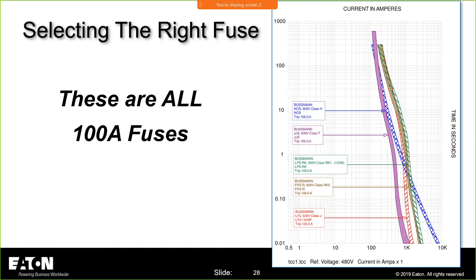So this is your Class T. Remember I said love at first sight? Look at that fuse curve. It's very fast. It's moved over to the left. This is a 100 amp fuse. I still get a nice little delay in here. So if I had a motor starting curve, or if I had an inrush current, maybe this little hump will hurt me. But again, you would always want to plot this along with your motor start curve or your transformer inrush to make sure you're covered there.